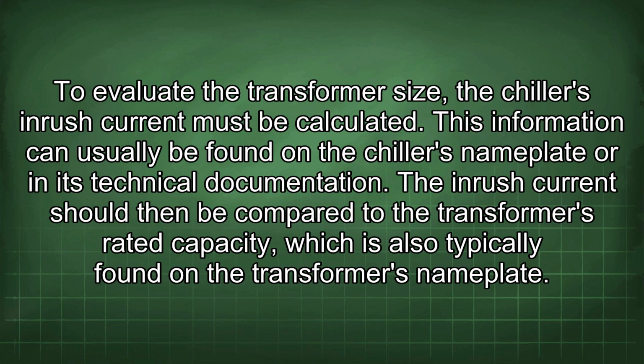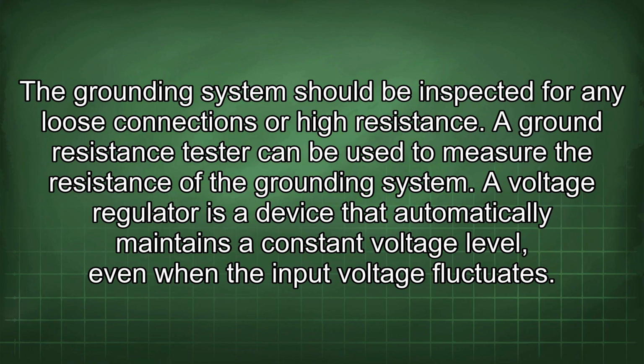To evaluate the transformer size, the chiller's inrush current must be calculated. This information can usually be found on the chiller's nameplate or in its technical documentation. The inrush current should then be compared to the transformer's rated capacity, which is also typically found on the transformer's nameplate. The grounding system should be inspected for any loose connections or high resistance. A ground resistance tester can be used to measure the resistance of the grounding system.